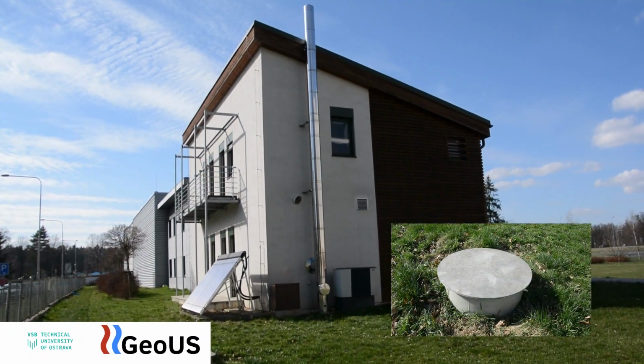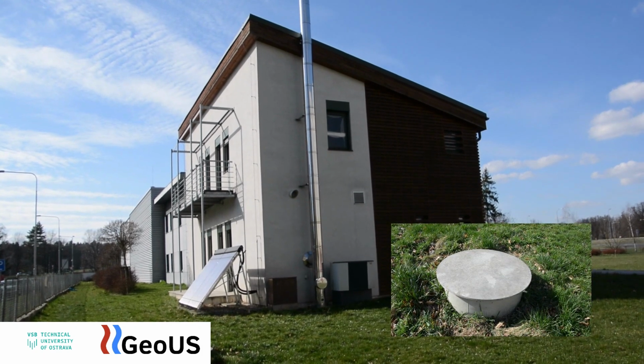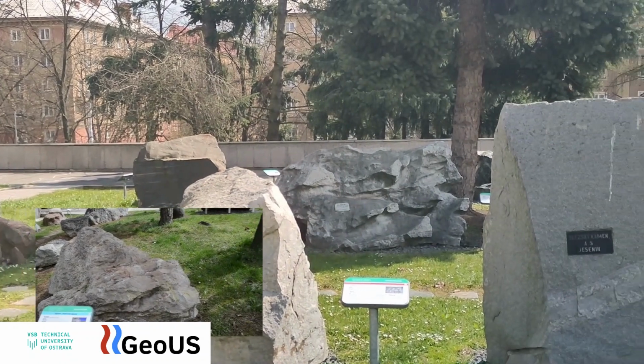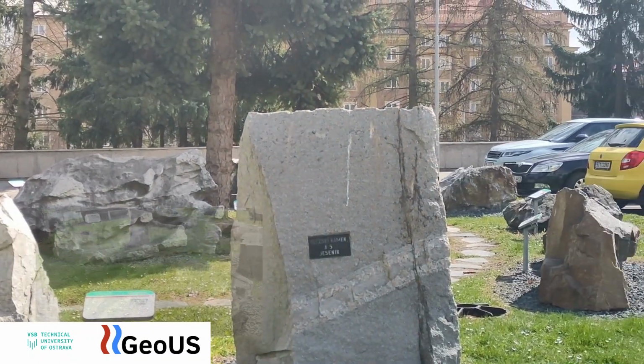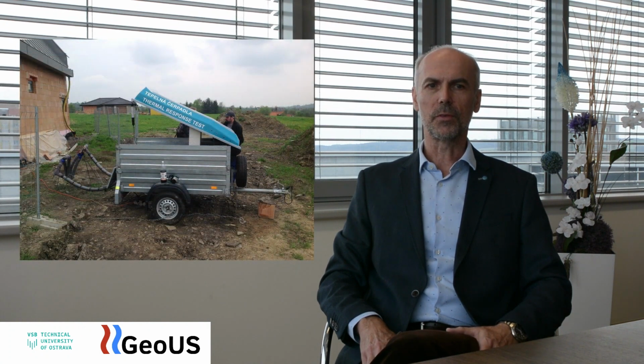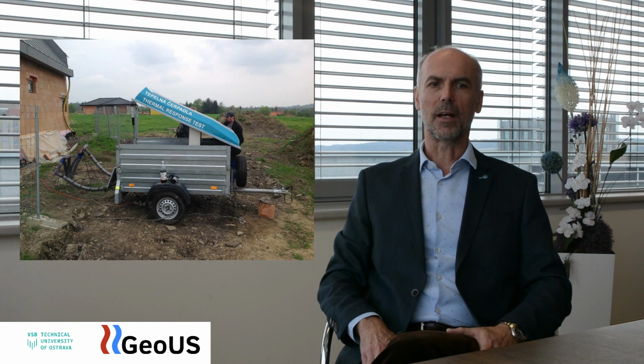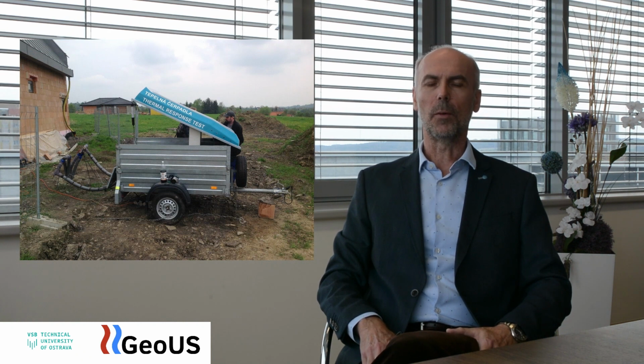When geothermal energy is required to heat and cool a building, the heat losses and gains of the building must be taken into account. The parameters to be determined for the rock environment are mainly thermal conductivity and heat capacity. In the case of large installations consisting of more than 10 boreholes, it is advisable to rely on measured values obtained from a thermal response test.